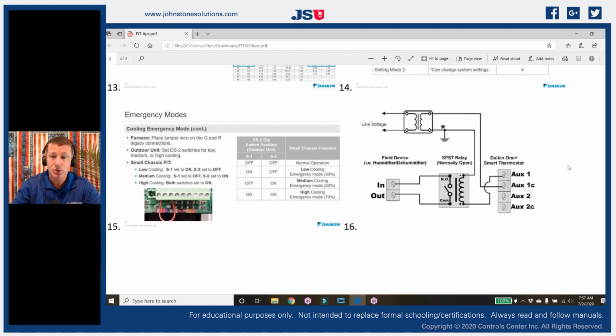It will just use those temperature sensors and pressure transducers to modulate the temperature on the coil. And so we can put those in a locked-in capacity. So we can go to our dip switches on our particular brand, on our Daikin stuff. It's on DS2. We can go to DS2 and we can lock it into 30% emergency run. We can lock it into 50% emergency run, or we can lock it into 70% emergency run. So it's just a matter of locking it into place.